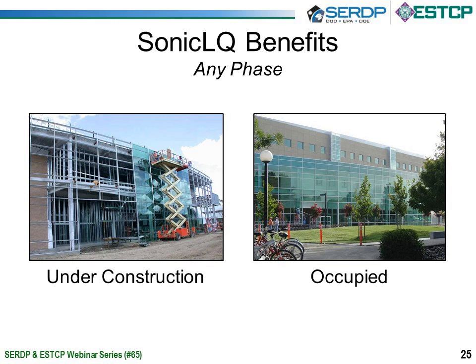So when you want to test a building that you're going to retrofit, to say, all right, how much might I be able to save in energy by reducing air leakage? You don't have to wait until that building is not in use. You don't have to come in and do testing in the middle of the night in an office. You don't have to wait till troops are out on maneuvers to go do some of the residential barracks. You can do this while the building's occupied.